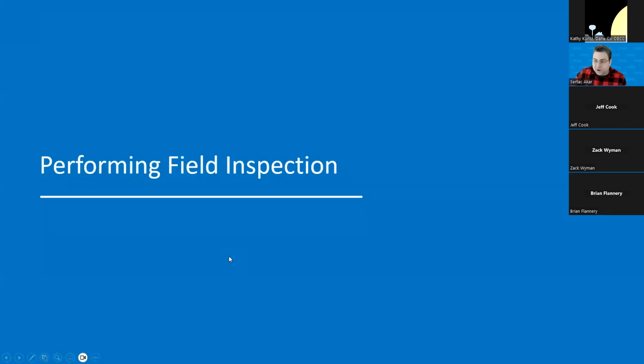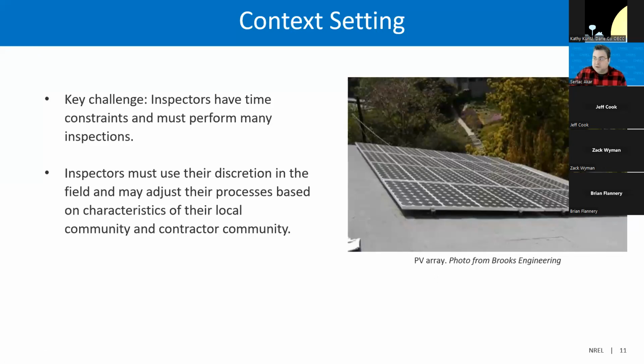So coming to the performing of field inspection, before starting the inspection, the inspector should ensure the system is not energized. The best place to start the inspection is the solar array, and the electrical path can be followed to the grid point. During that, the inspector should look for the most common and most serious code violations. If the time is limited, the inspector can focus on the inverter, array, grid connection, and junction boxes, which is where the most common code violations are actually located.